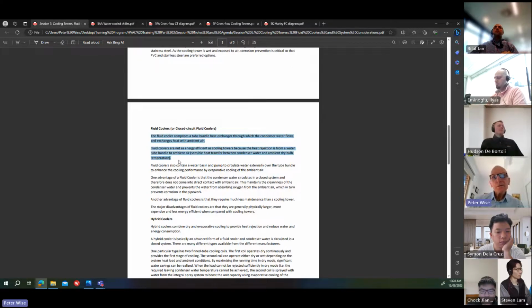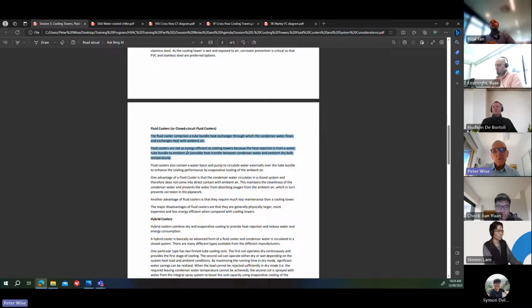They're not as energy efficient as cooling towers because the heat rejection is from a water tube bundle to ambient air. So it's a sensible heat transfer going on between condenser water and ambient dry bulb temperature. The wet bulb temperature, as you know, is always less than the dry bulb. So with a cooling tower, you've got a bigger potential, bigger temperature difference, and you've got evaporative cooling working, which gives greater performance.